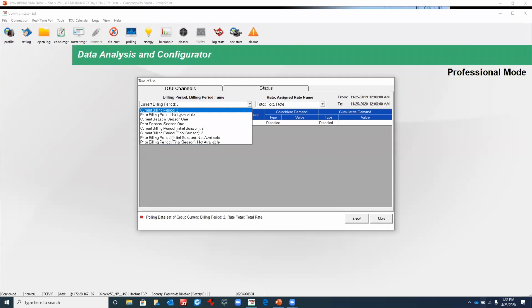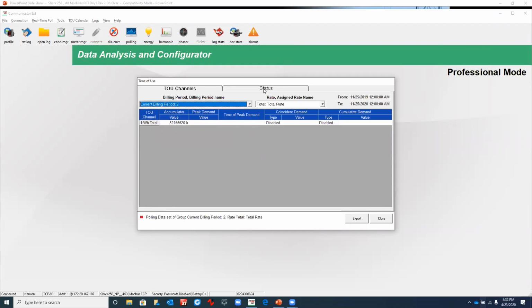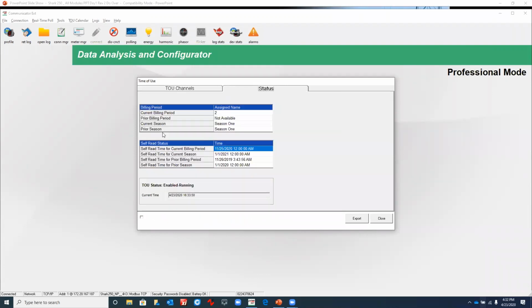Here it's typically set up by seasons, prior billing information, current seasons, and so on. So this is stored in the meter, and the meter would automatically save the information for retrieval at some point. If you look at the status, once we set those up, we can see the various seasons that we're looking for if you're looking for billing period information.